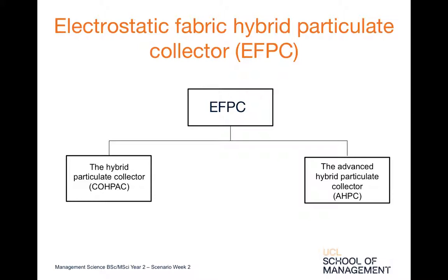It is interesting to note that such systems are already being implemented in the US and China. In China, the EFPC used in power plants are similar to the COHPAC type. Zhejiang FEIDA Environmental Science and Technology Company has installed several separated and integrated types of EFPC. For the integrated type, the biggest one is used for a 200 MW unit in the Baotou power plant. EFPC systems have since been installed on bigger power plants, such as the Jharsuguda power plant of India, which was installed downstream of 6 times 600 MW units.